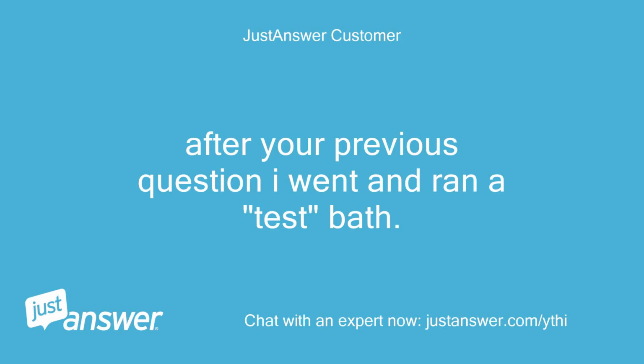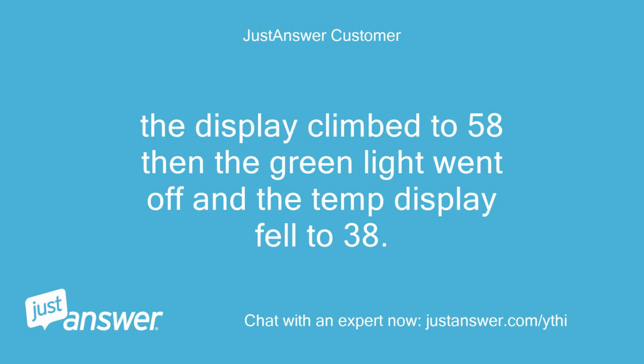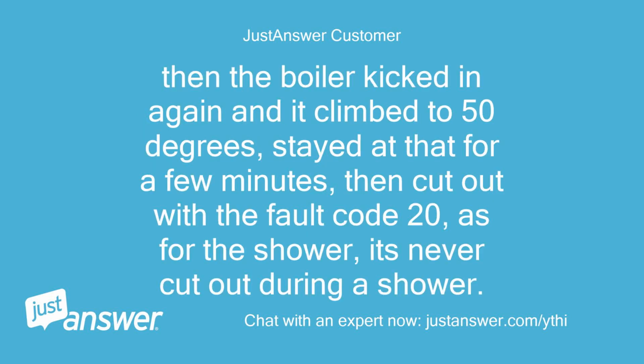After your previous question, I went and ran a test bath. I've got the hot water set to 58 degrees. The display climbed to 58, then the green light went off, and the temp display fell to 38. Then the boiler kicked in again and it climbed to 50 degrees, stayed at that for a few minutes, then cut out with a fault code 20. As for the shower, it's never cut out during a shower.